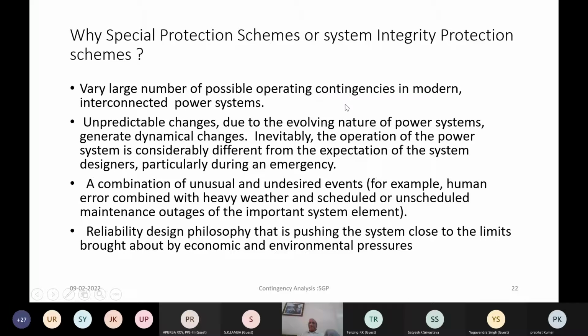There are a very large number of possible operating contingencies in the modern interconnected electrical power system. Now, when the regions were not interconnected, the effect of one region on another region was very minimal. Even if you have, say, DC interconnection, then also there is a sort of isolation of disturbance from one region to another region. But with the AC interconnection, with all the regions, with the Indian power system operating in a synchronous way as a single area, there are a very large number of possible operating conditions for which you need to plan measures. And that's why these complex contingency and state estimation programs need to be totally automated so that actions can be done in an automatic manner. And again, the phasor measurement unit and its technology is going to play a larger role in future.